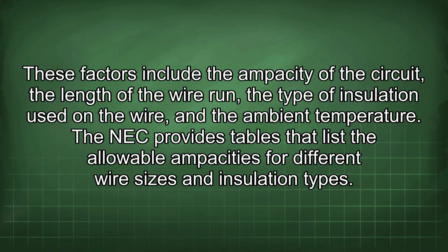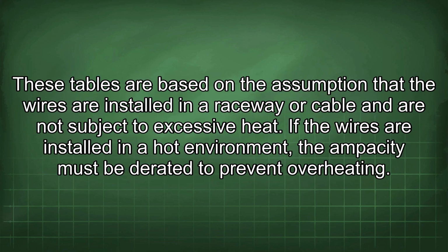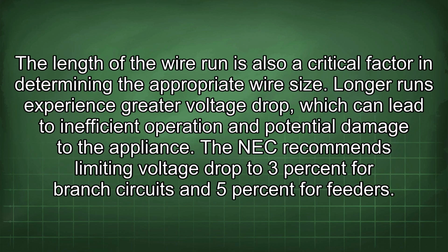The NEC provides tables that list the allowable ampacities for different wire sizes and insulation types. These tables are based on the assumption that the wires are installed in a raceway or cable and are not subject to excessive heat. If the wires are installed in a hot environment, the ampacity must be derated to prevent overheating. The length of the wire run is also a critical factor in determining the appropriate wire size. Longer runs experience greater voltage drop, which can lead to inefficient operation and potential damage to the appliance. The NEC recommends limiting voltage drop to 3% for branch circuits and 5% for feeders.